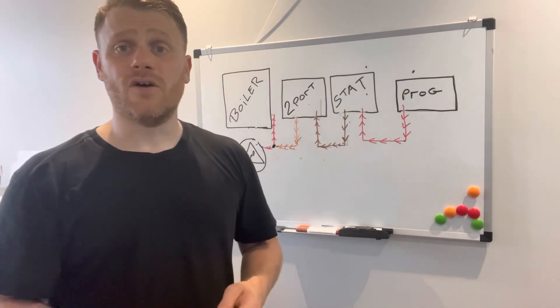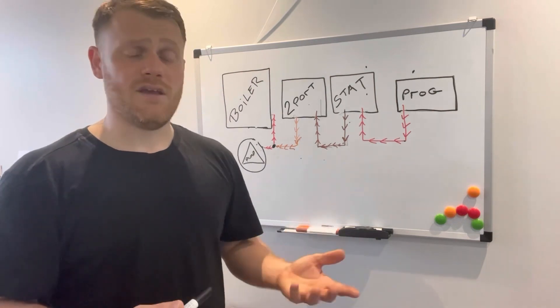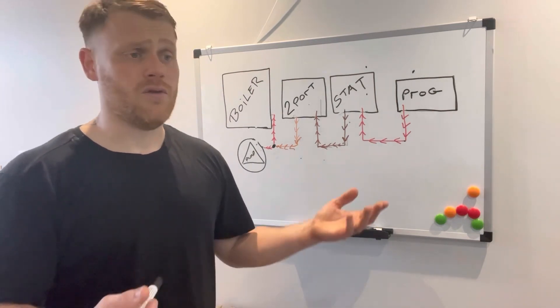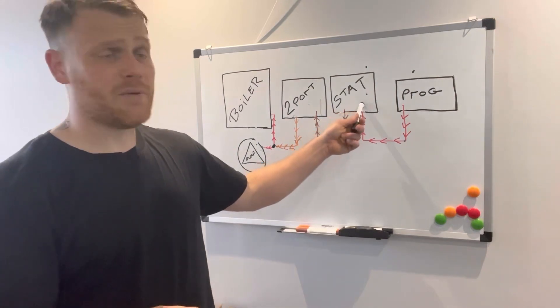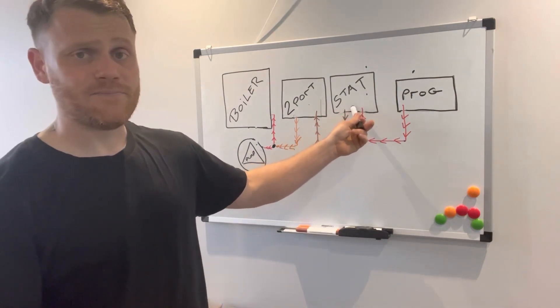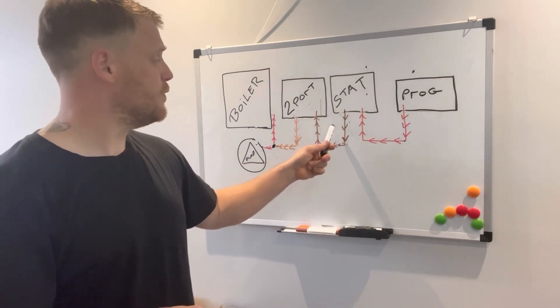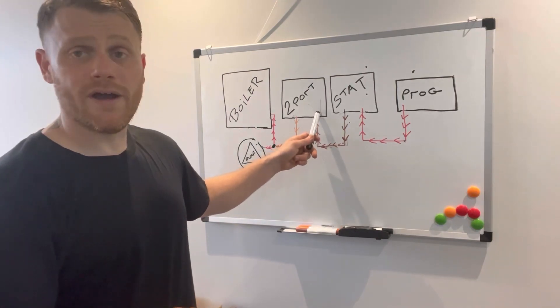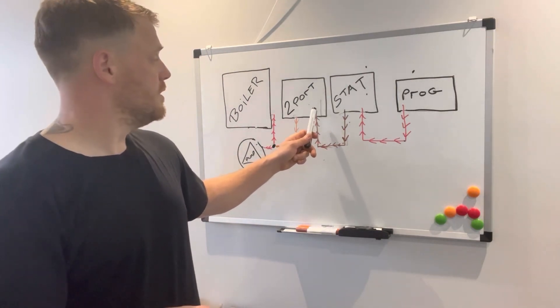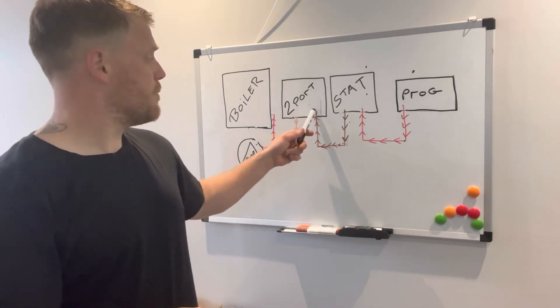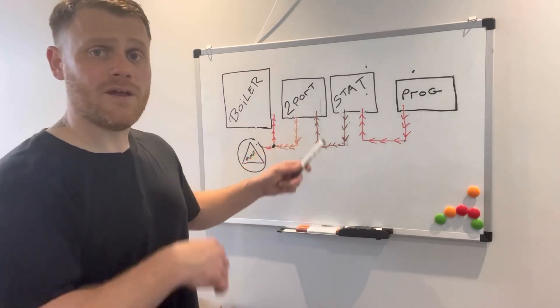That can be your room stat or your hot water cylinder stat. Now if that's got a demand, so if the hot water needs heating or the central heating needs to come on, that'll be calling. That'll make the switch in here and that'll send 240 volts then to your brown wire on your two-port.